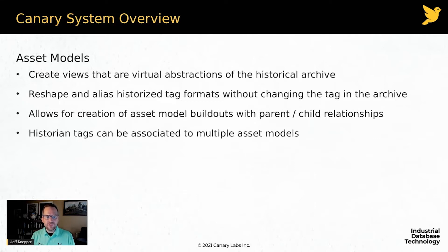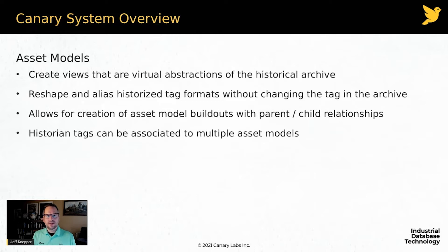Most importantly, I can place a single tag from my archive into multiple versions of these models. I could have a model focused on production, with tags that live in that model, as well as a different asset model that is more maintenance-oriented, or oriented by the engineer responsible for those pieces of equipment.